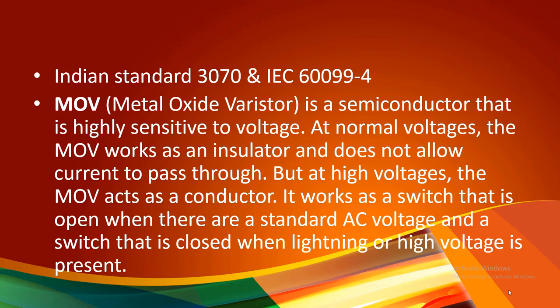So the surge arrester consists of: a high voltage terminal, a ground terminal, MOV blocks, a diaphragm for pressure release, and a cap — all part of the metal oxide varistor-based surge arrester. Regarding Indian standards, IS 3070 covers the complete study of surge arresters — scope, normal conditions, and design parameters. IEC 60099-4 is the international standard. These two standards are designed for surge arresters.